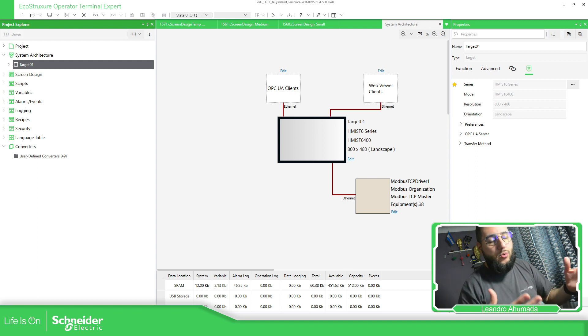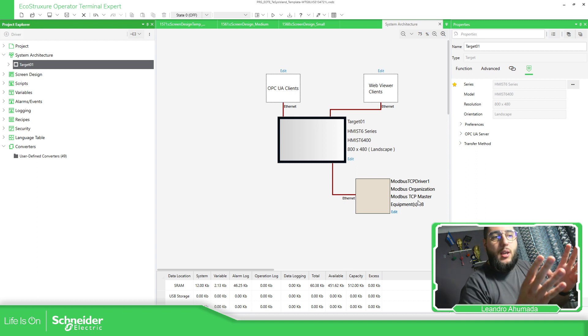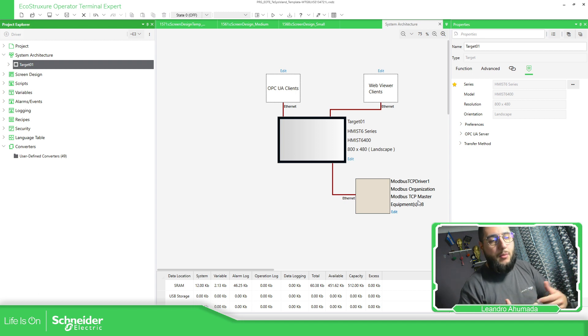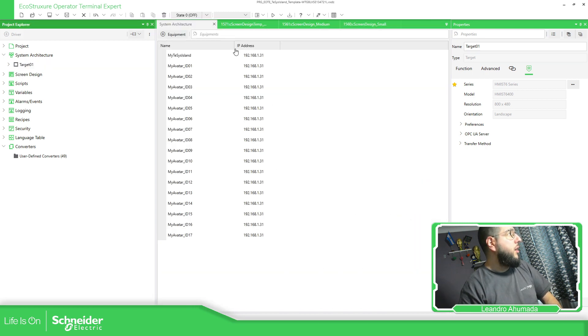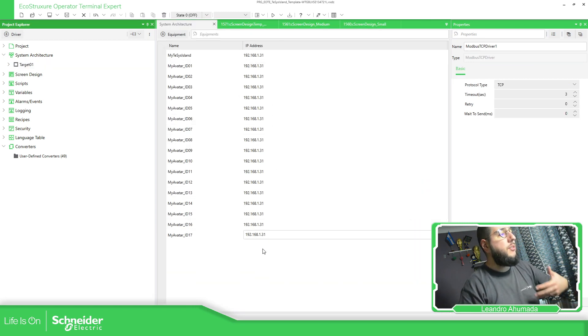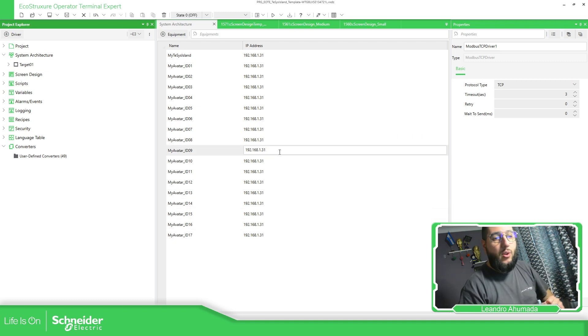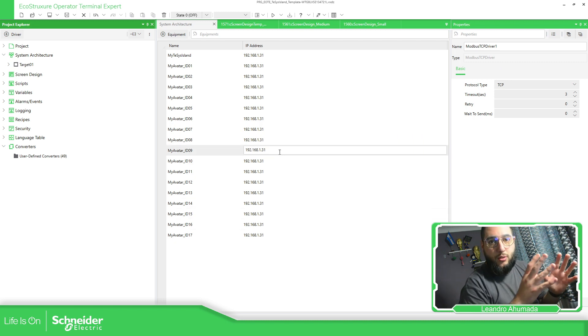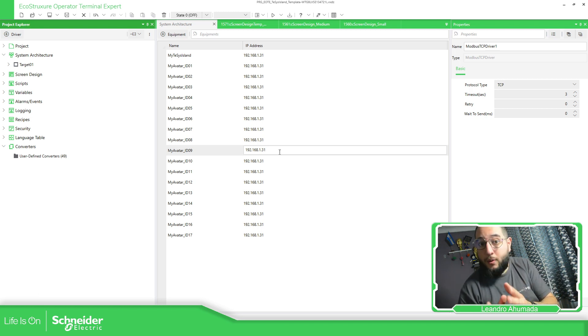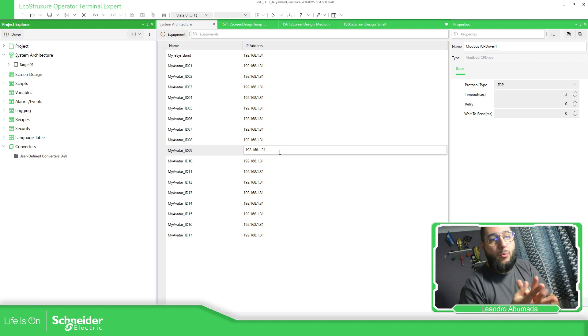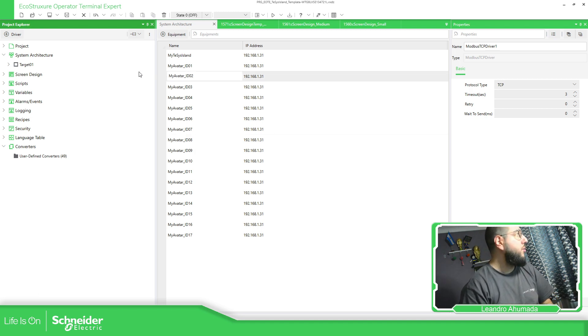Each avatar has its own unit ID depending on the device you're using. What I have done here is pre-configure some avatars with the same IP address as the Tesys Island. In order to connect, the Tesys Island needs to be on Modbus TCP and you need to have an IP address already defined, so we can communicate using the HMI.